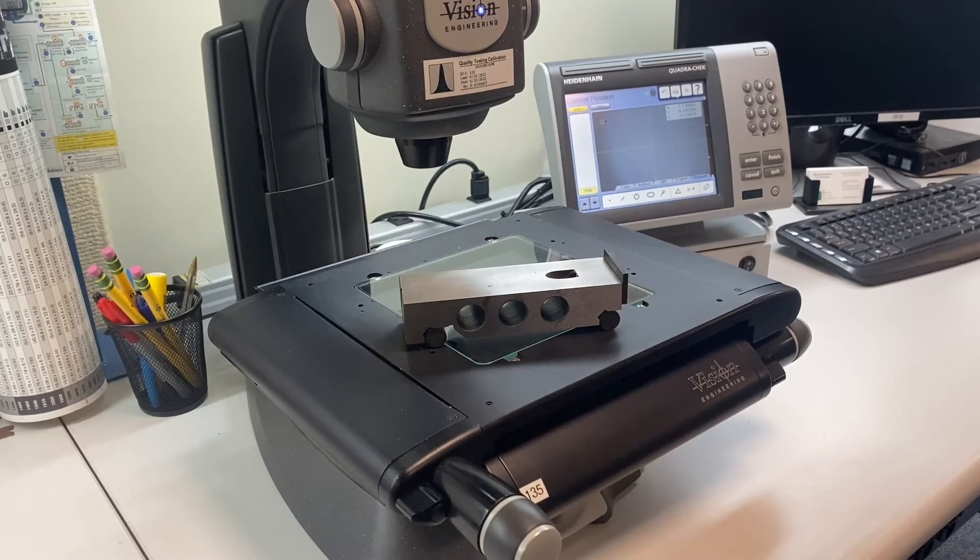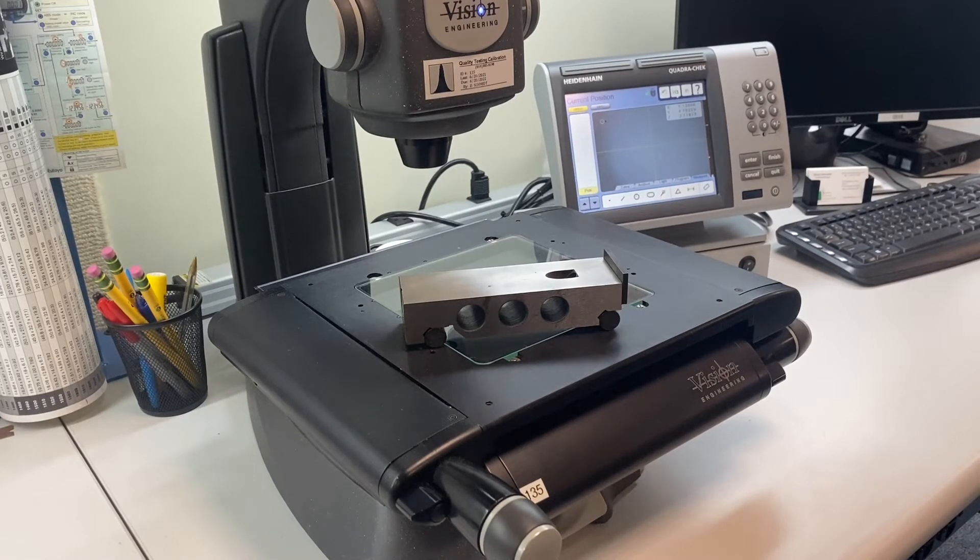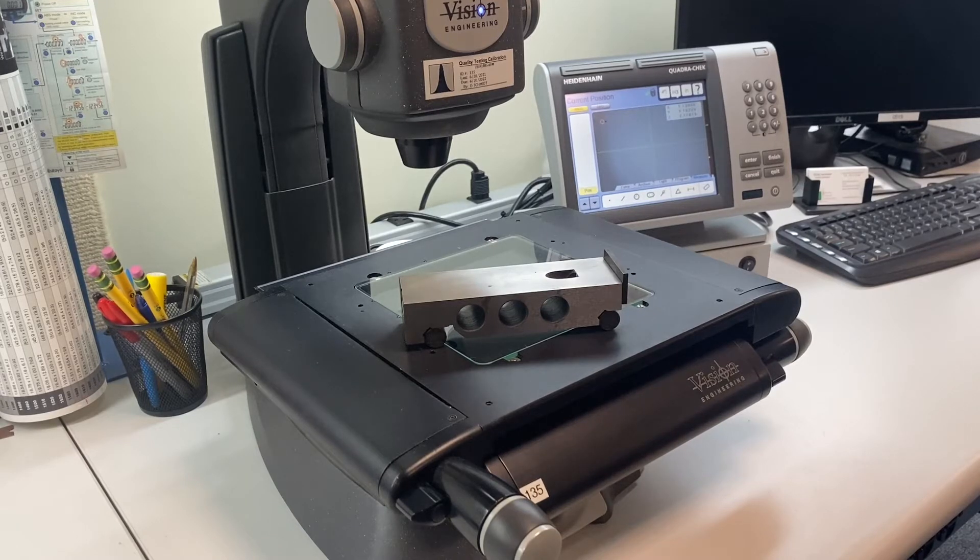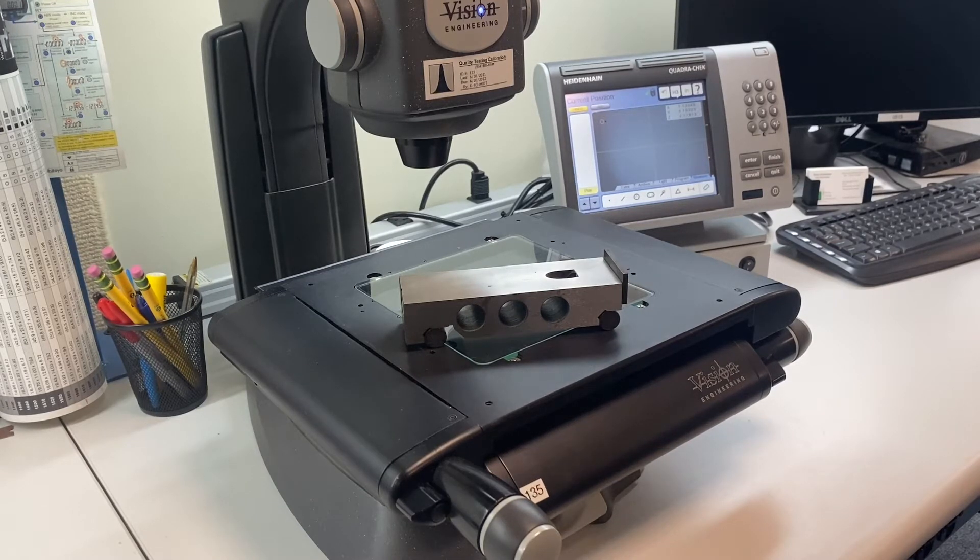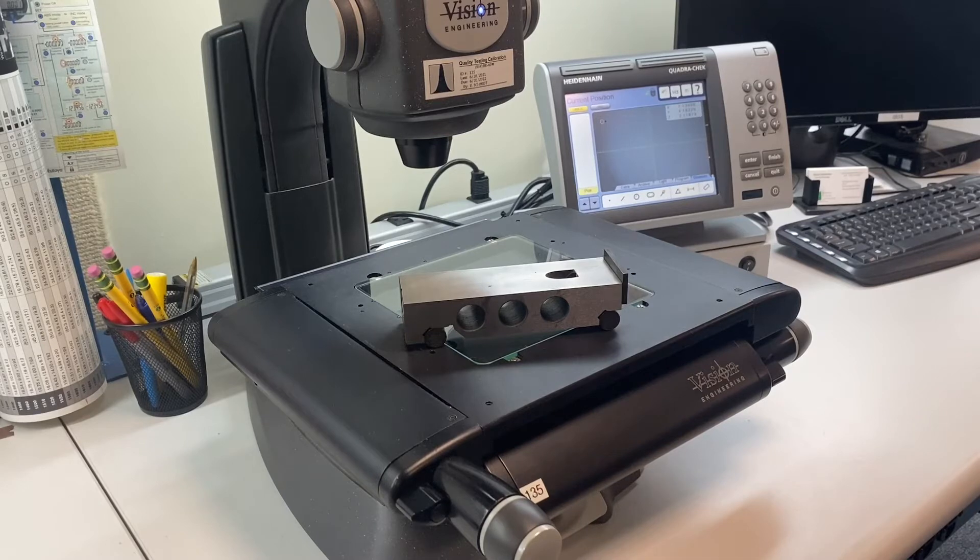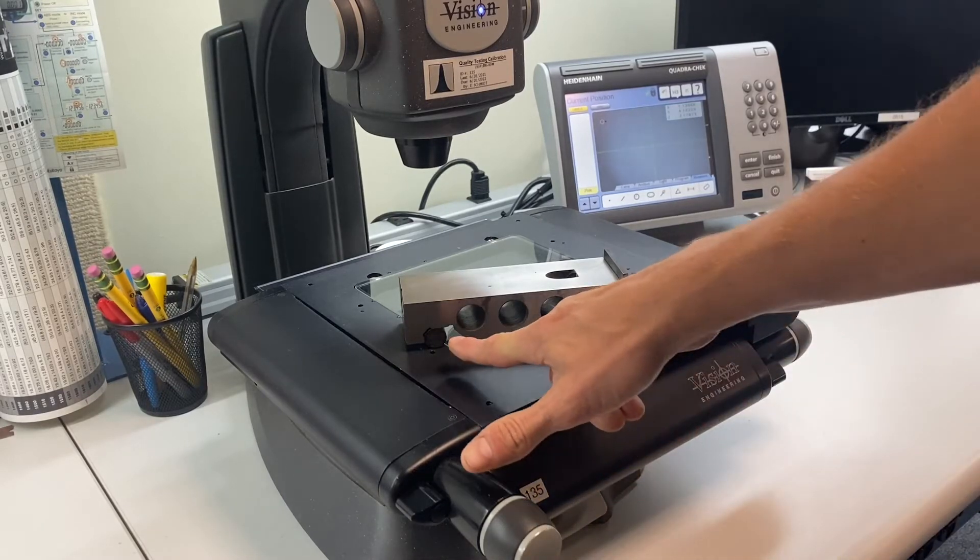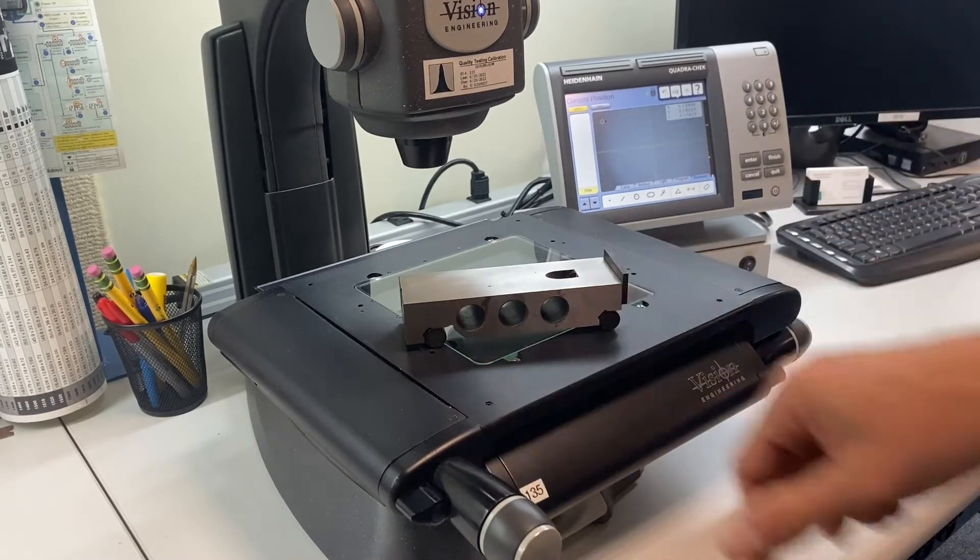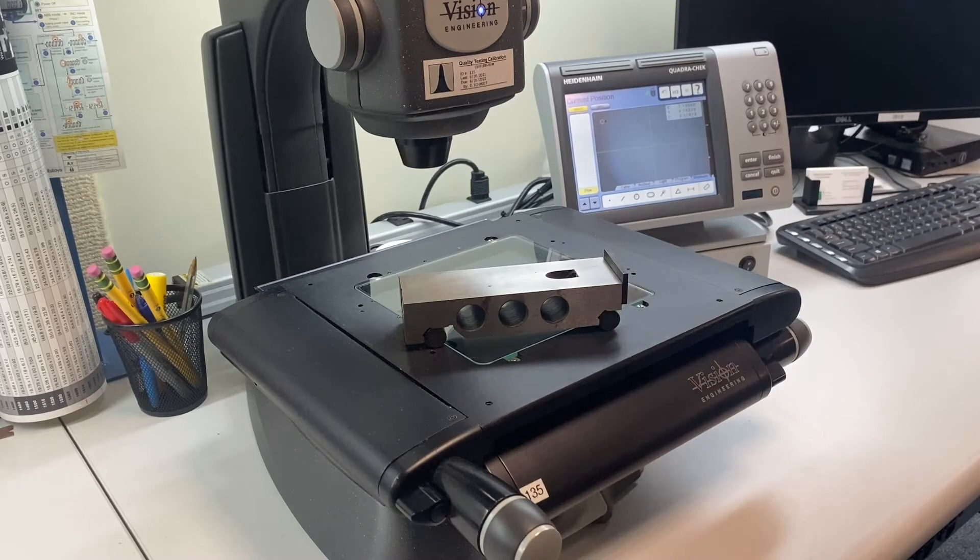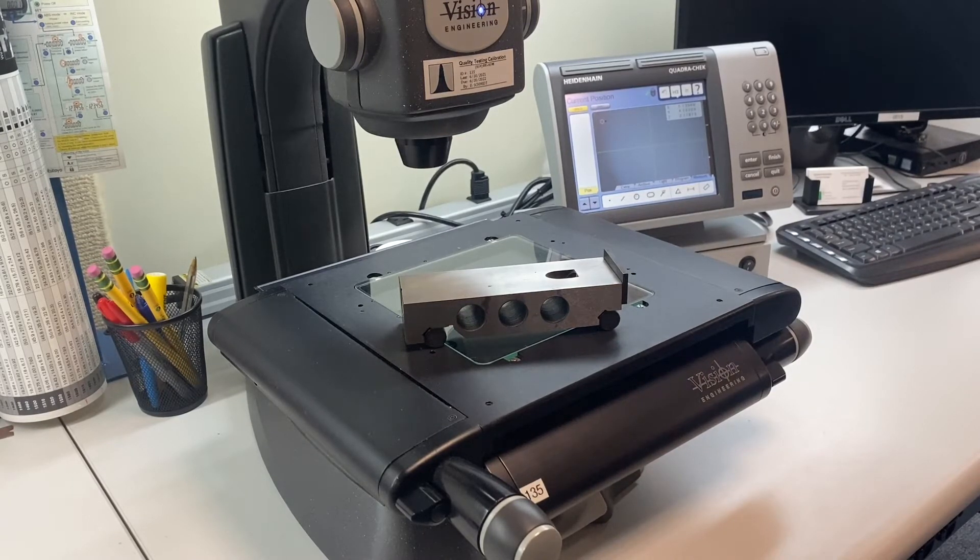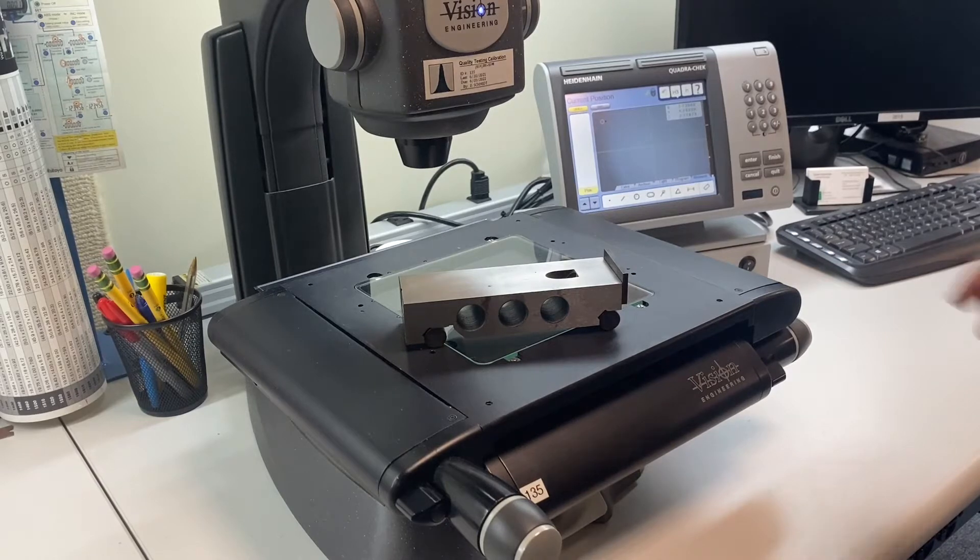In this video we'll be demonstrating how to calibrate a sine bar. This is the first step in the measurement where we measure the distance between the pins. It should be about five inches, so we're going to use this vision system to measure the distance between the pins.